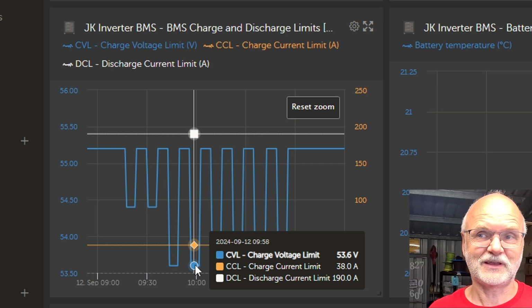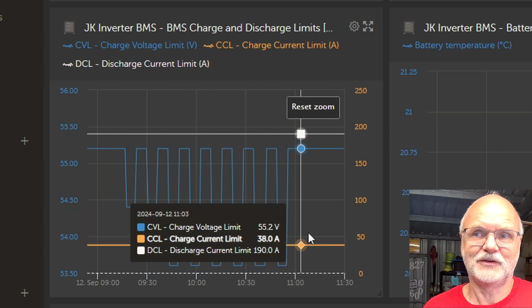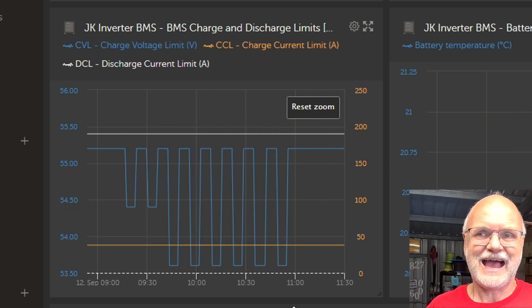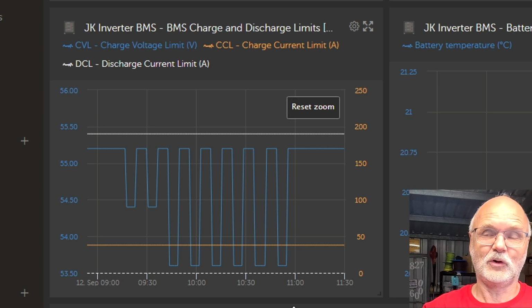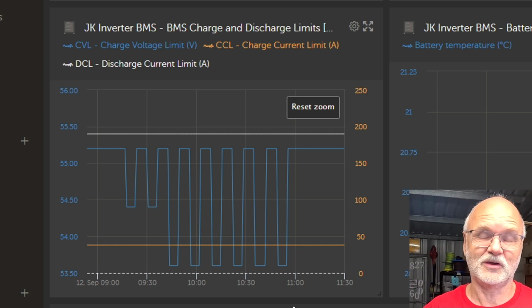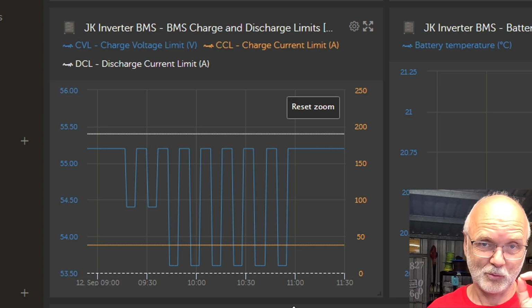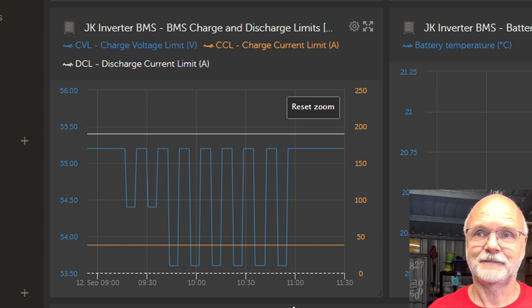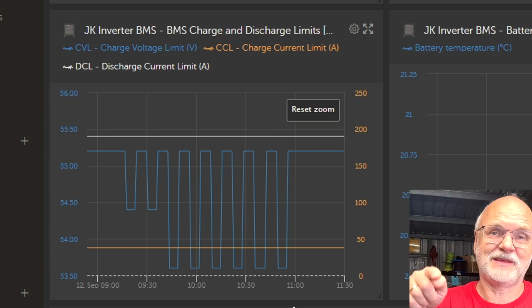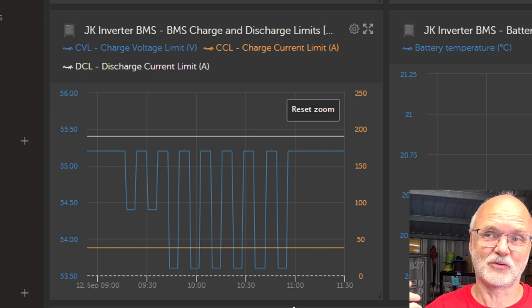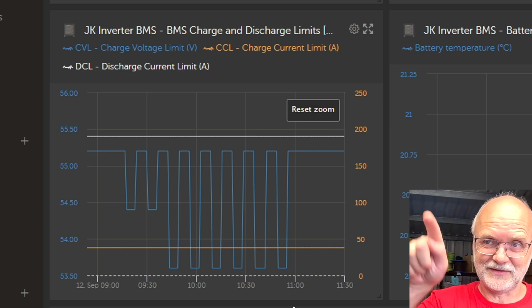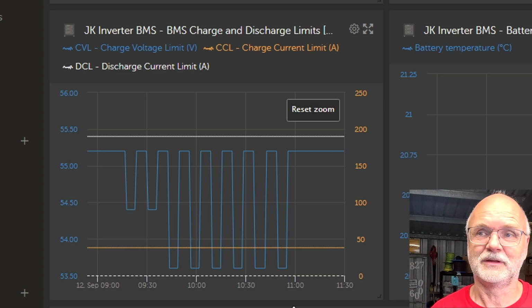Requesting 53.6. I let this run for an hour or so, and you can clearly see how the absorption and the float voltage are requested from your inverter or the Victron system. It works perfectly again. For testing purposes, I set both timers to 6 minutes so we can see these rectangles going up and down.